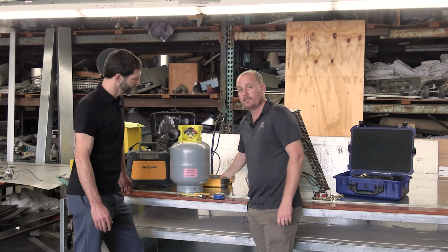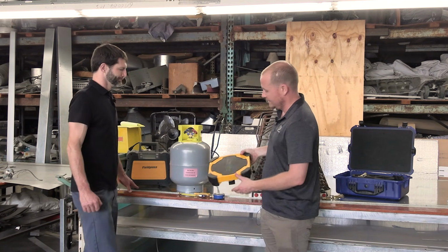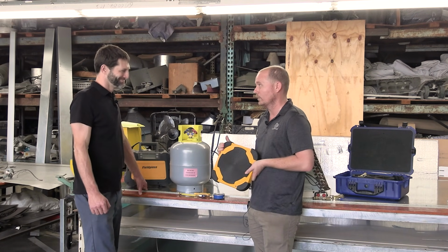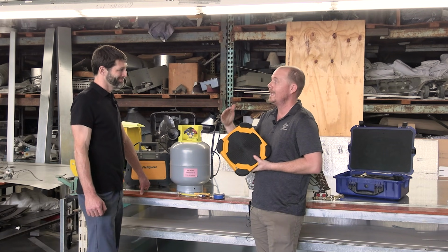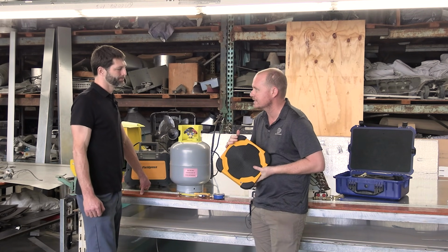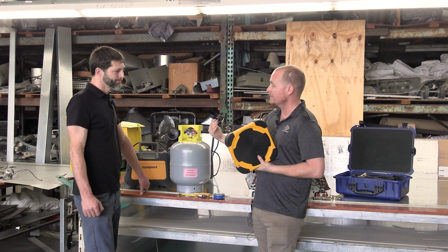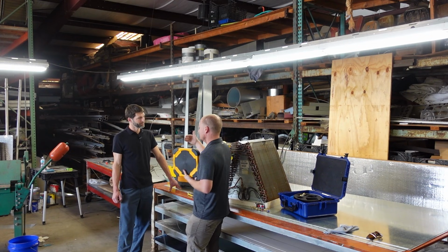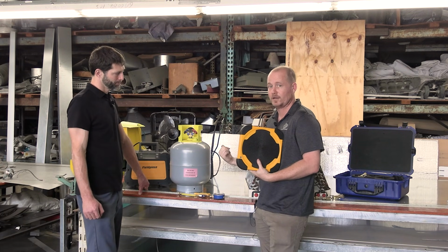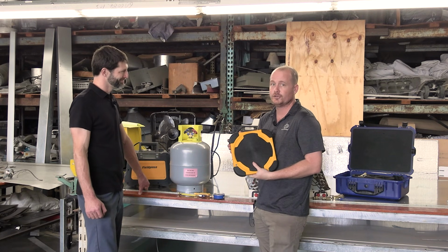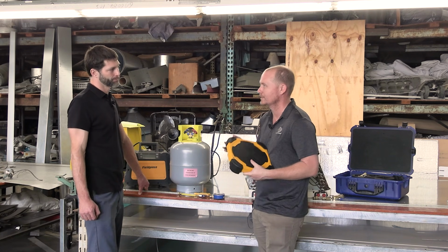Having this scale out from the very beginning, just making sure this sucker's out and ready to work with, is a really big thing anytime you're charging into a system, anytime you're recovering from a system, because it's also going to be really telltale if, say, you're replacing that compressor and when you're recovering the charge, you find that the system only has half the refrigerant it's supposed to have.